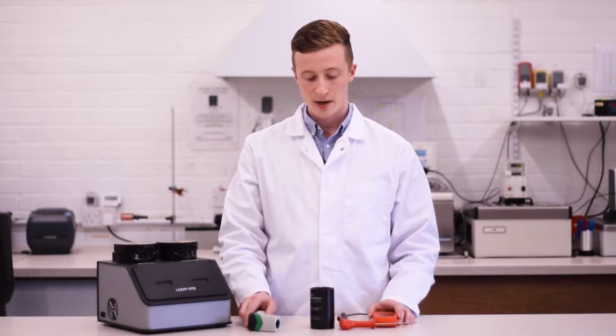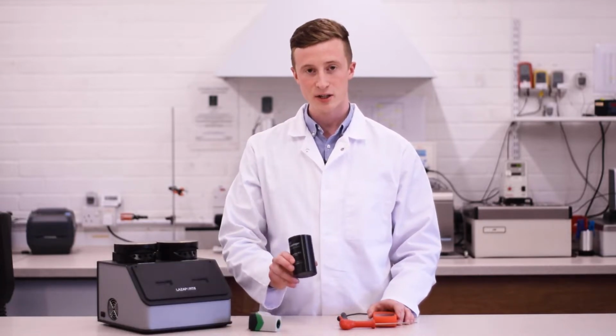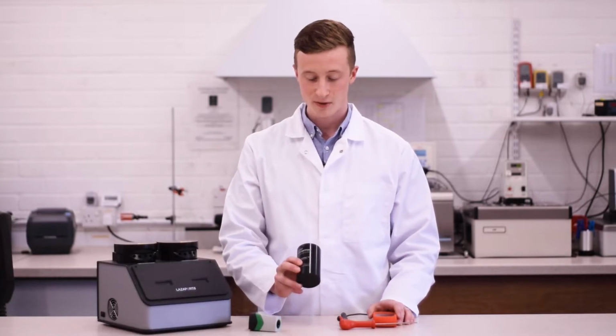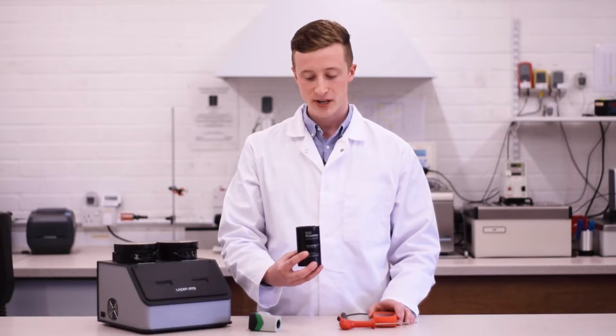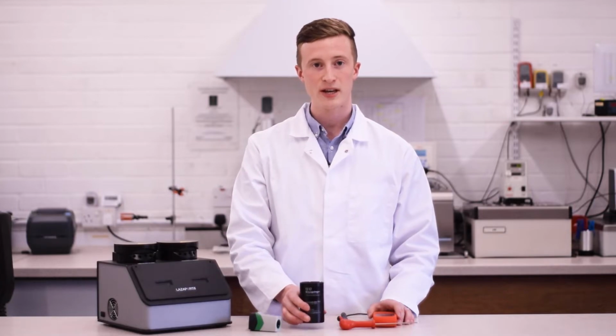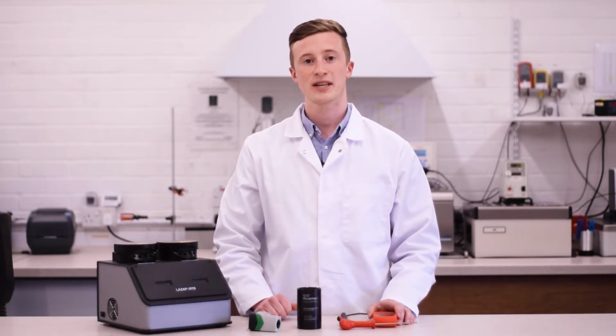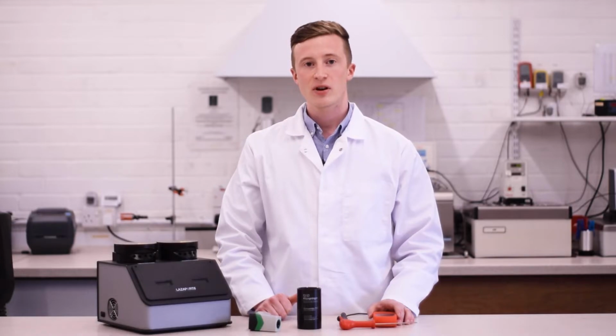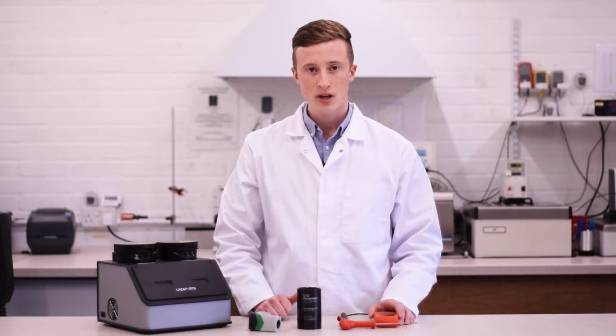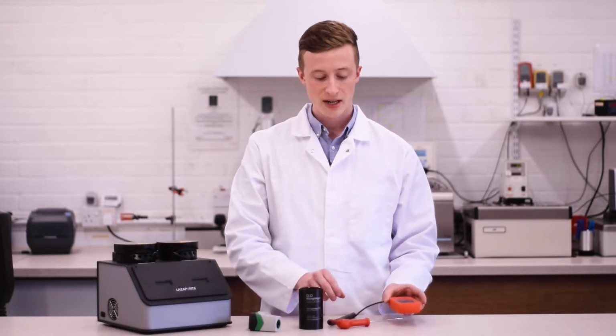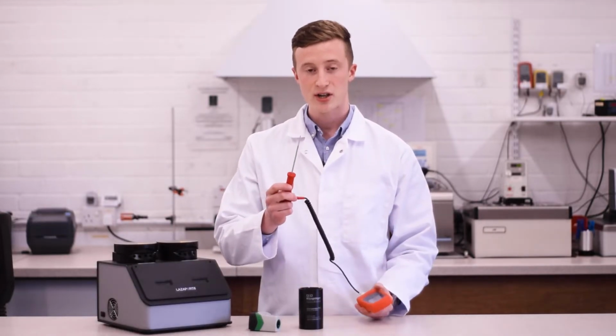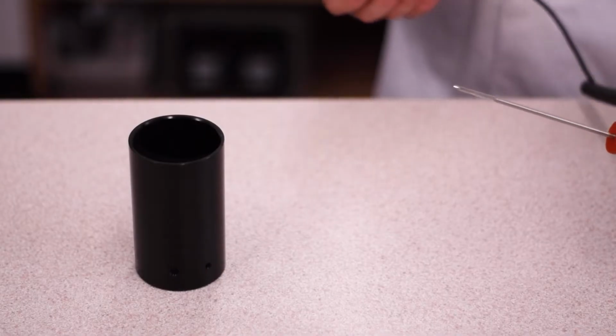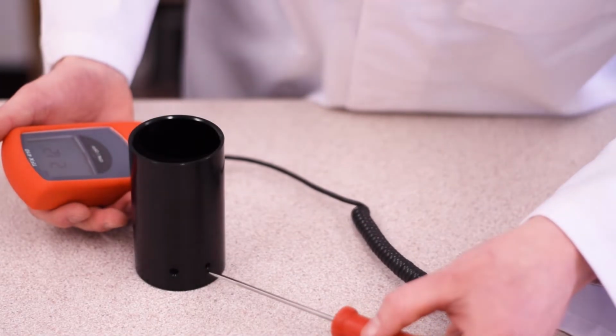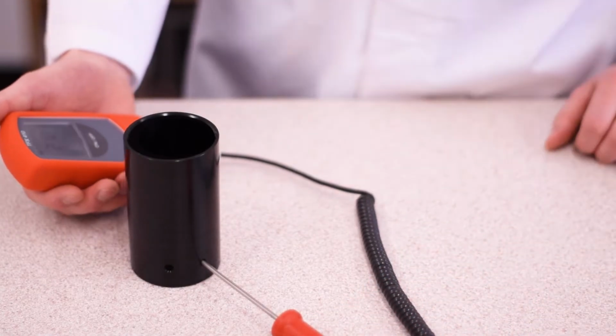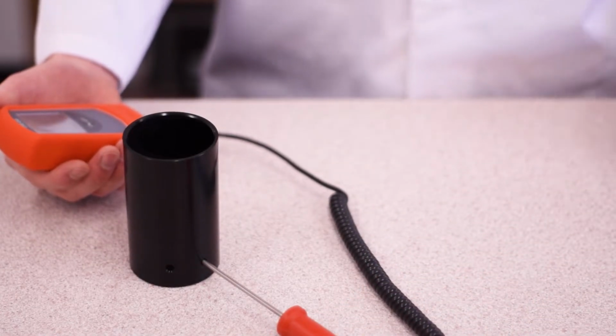Firstly, use a comparator pot. This is a small, simple device like you see in front of me here. To start, it's important you put the comparator pot in the room where the verification will be taking place. Leave it to stabilise with the room temperature for at least 1 hour. To use a comparator pot, you also need a reference thermometer with a penetration probe or similar. Insert this into the reference port in the base of the comparator pot. Leave your reference thermometer to stabilise.